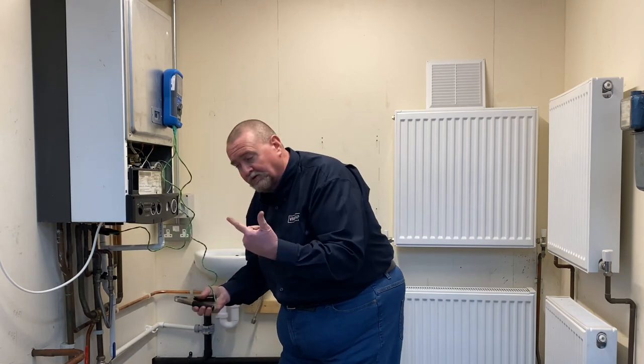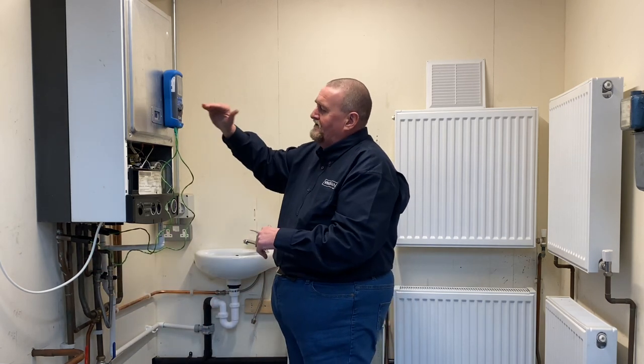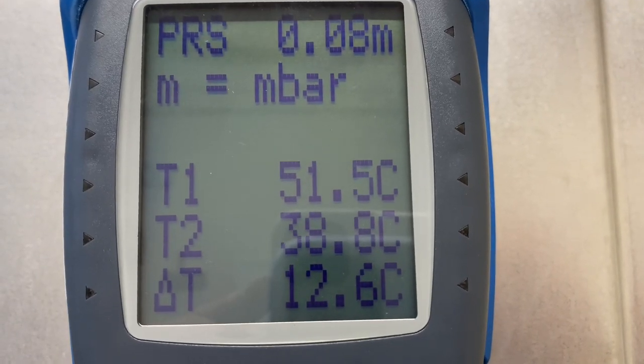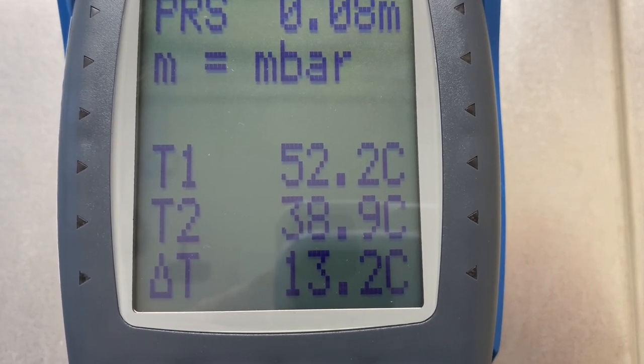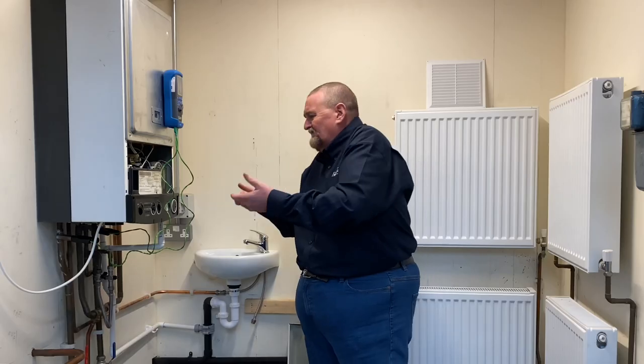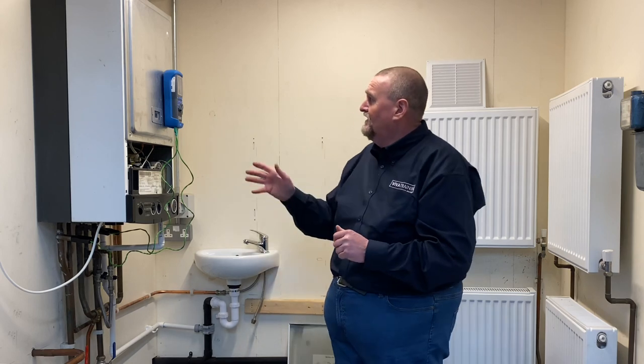Under this particular boiler there are a couple of sockets where the tails are, so that's ideal because I know those sockets are equal distance. I'm just waiting for it to settle out. The boiler temperature on the front is showing around 50 to 60 degrees. Now I've got a flow temperature of 51 degrees, a return temperature of 38 degrees, which gives me a differential of about 13 degrees. On a standard efficiency system we're looking for around 11 to 12 degrees differential; on a full condensing system we're looking around 20 degrees differential. So I know I've got good circulation around this heating system.